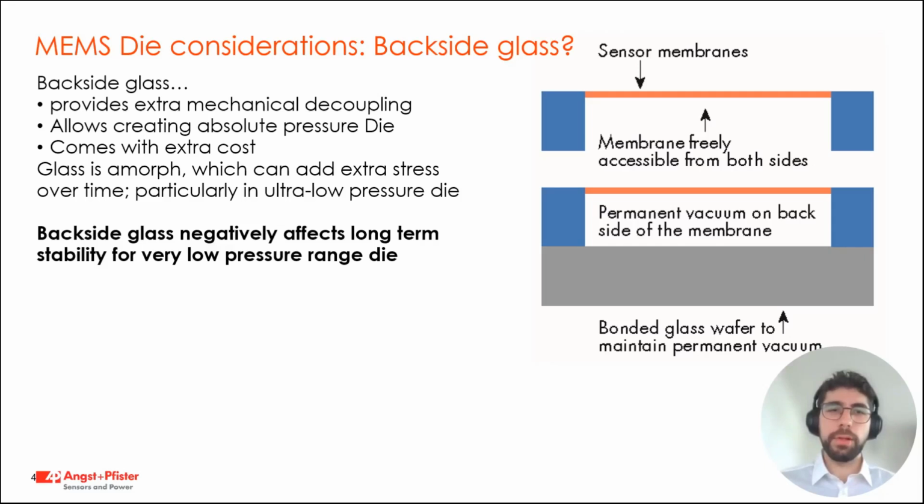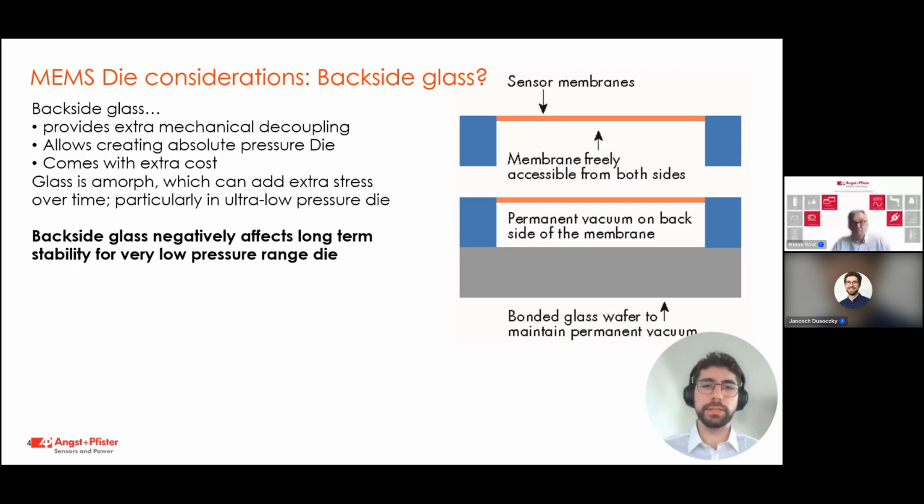For example, with just two open tubes attached to a sensor with our die in, there is a clear pressure signal if the door of a room is being closed or opened. For this reason, in many applications, it is impossible to do a zero offset calibration, and therefore the drift has to be stable throughout the lifetime of the sensor system.